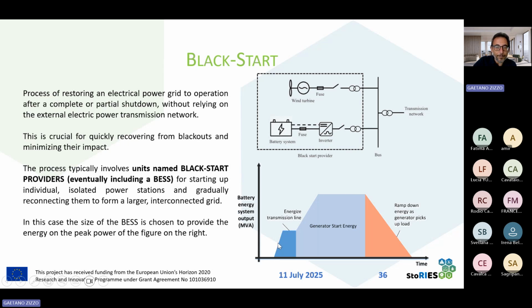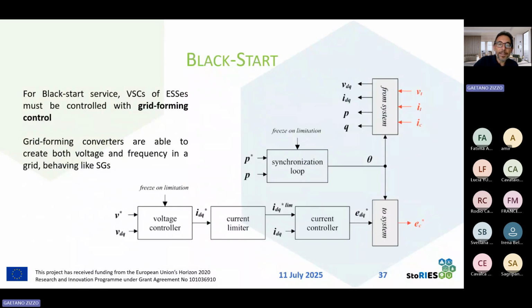You can see that in a first phase, we have to energize the transmission line. Then we will connect the black start provider to a transmission line. We will energize the transmission line. Then we close the switch that connects the generator to the line, and we energize the generator. So the generator takes from the storage the energy needed for restarting, and then we have a ramp down of the energy for reducing the load. For doing this, it's important that the VSC converter coupled to the BESS is controlled with the grid forming control.